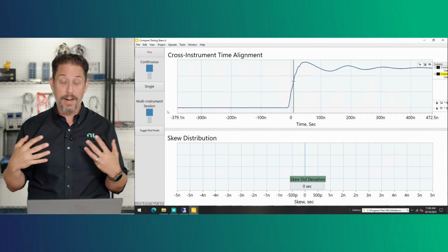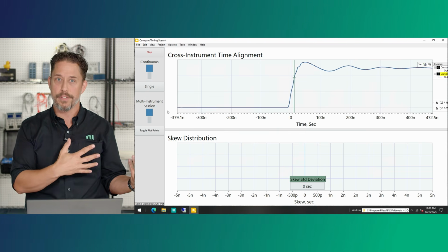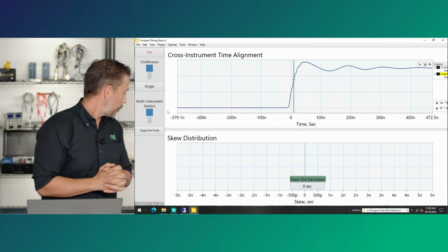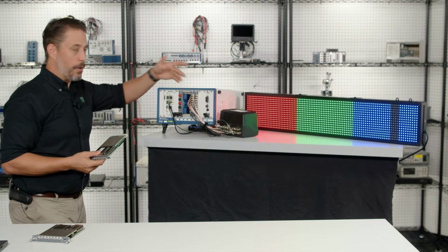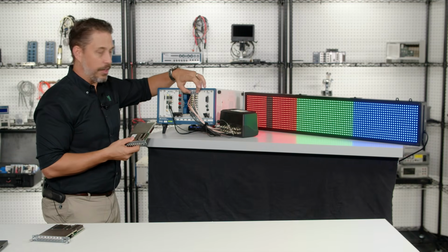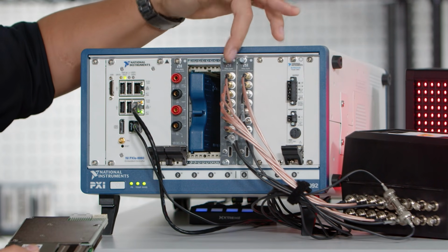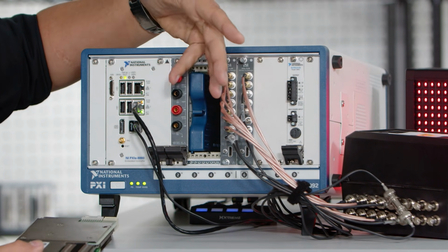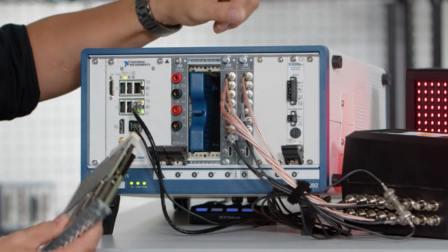Now, taking a step back from looking at it in code, what would that look like with the physical hardware setup that we've got? So what we know is that within the system that we have here, we've got our two 5108 modules, each supplying 8 channels, and you saw it working, all of them acting as a single oscilloscope.